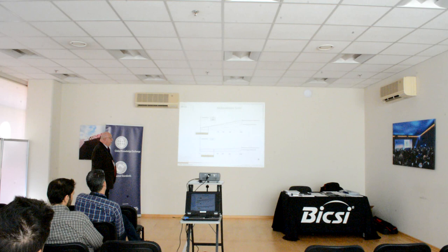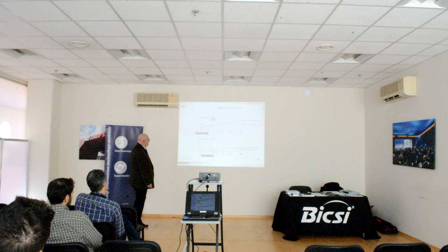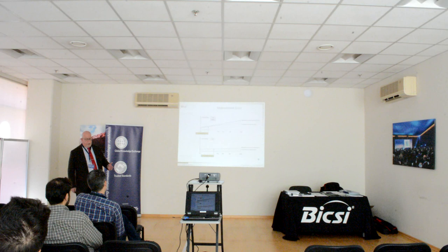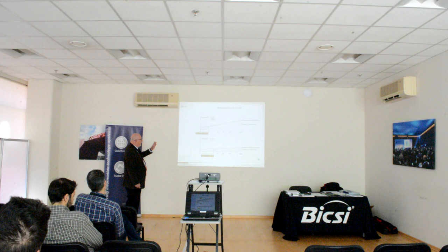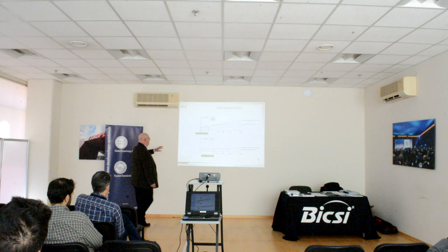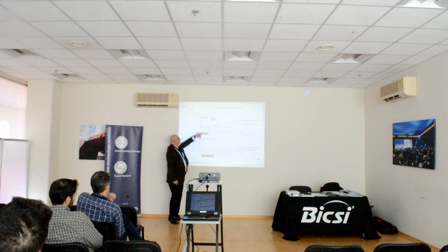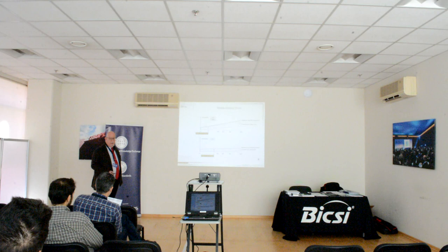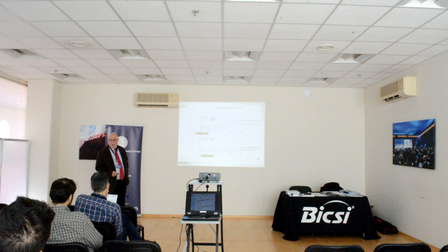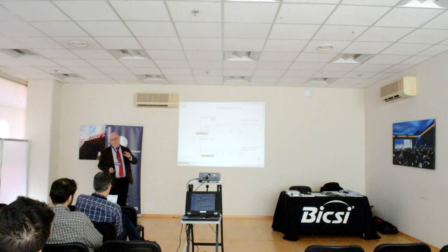The problem is, for installers, if they're not clever enough to realise that you've got a measurement error, which means that when you measure something it can be plus or minus a little bit due to the test equipment, the test leads, the test method, then as you start to reduce the lengths, there's a risk at some point where you start finding that you get results which are worse than the specified maximum, because the error, even though you're actually measuring that value, takes you over the top of the limit. And then people get very upset and they say, oh, we're not going to pay you because your results are bad, which is really, really harsh. But that is the natural outcome of trying to measure things that are smaller and smaller and smaller when you've got technology which has got limits in terms of its accuracy.